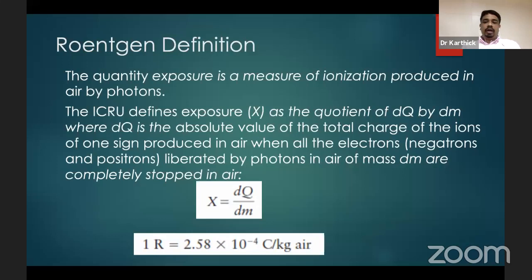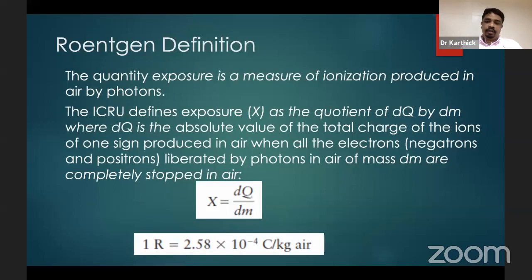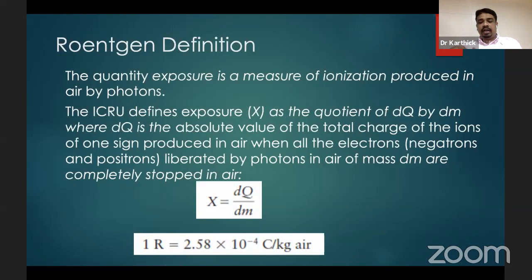The basic definition: the quantity of exposure is the ionization produced in air by photons. As per ICRU, exposure is defined as the quotient DQ/Dm, where DQ is the absolute value of the total charge of ions of one sign produced in air. Everything must be collected — we cannot leave any ion produced in the particular mass. We have to collect all the ions. One Roentgen equals 2.58 × 10⁻⁴ Coulomb per kilogram in air.